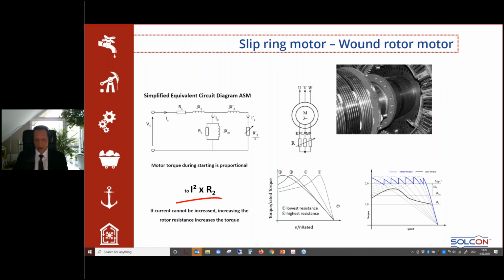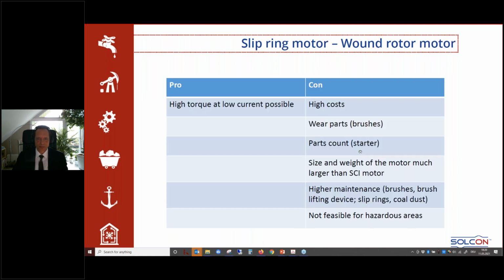And here you see, with more and more resistance in the rotor, the curve of the asynchronous starting is bent to the left side, and you have this kind of starting torque and current, and this can help you in very severe cases. But it comes along with high costs, with wear parts and parts count. Size and weight of the motor is much bigger than a squirrel cage induction motor, higher maintenance. It's not feasible for hazardous areas. And let's say the only segment where you find this still in large scale is cement.